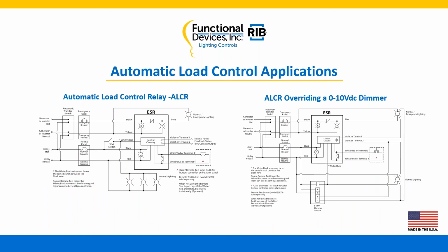Here is an application for one without 0 through 10, and then we'll talk about 0 through 10 volt dimming override here. Basically, as we talked about, you've got your ATS, automatic transfer switch, set up here. You've got your normal power here. We're actually feeding normal power. We've got a switch involved here, and our control circuitry is controlling the normal lights out here. We've got that on. We've got a normal emergency light up here in the upper right.